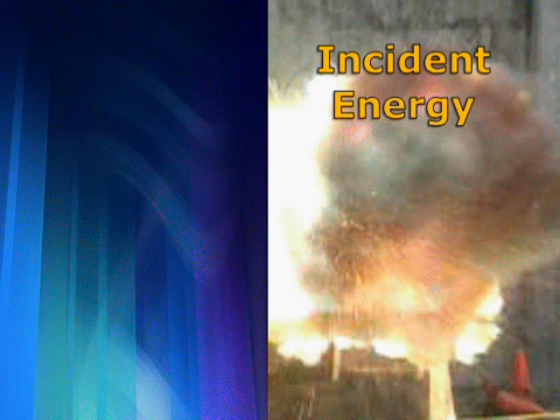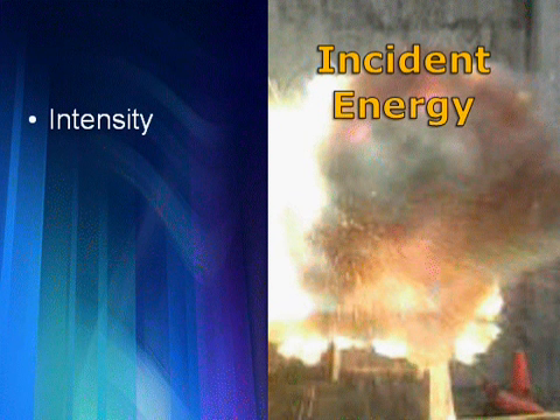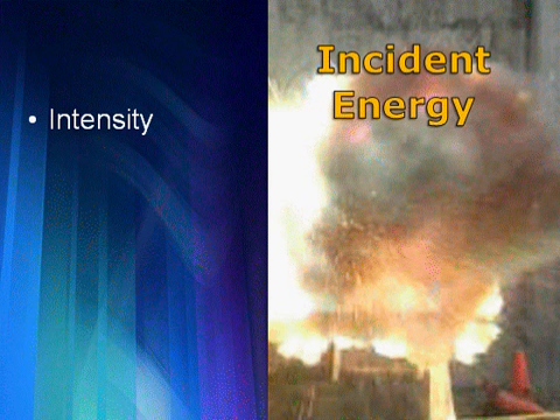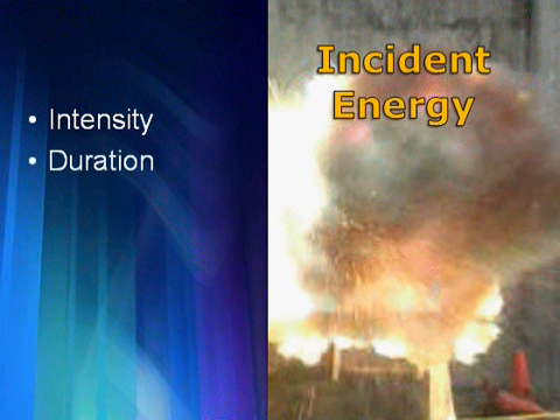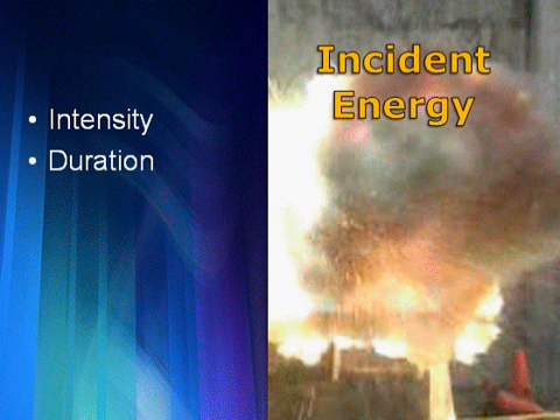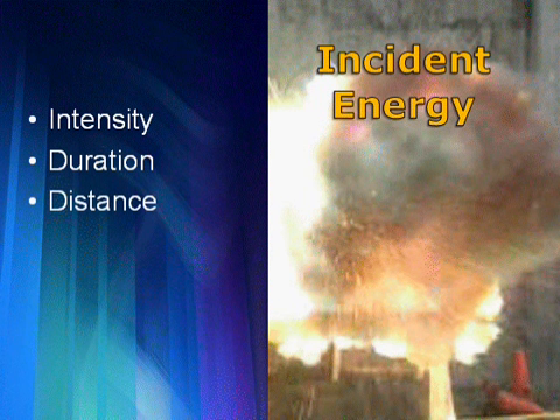You need to factor in things such as intensity. Now, intensity is not, I'll say, an official term, but it's a term that I've used a lot. It's really the short circuit current. The higher the short circuit current, the more intense the arc flash can become, but it's also dependent on duration. When you're looking at strictly incident energy, you can have a lot of short circuit current over a short duration, or maybe a lower short circuit current over a long duration, and you'll have the same amount of incident energy. But a more intense arc flash, well, that's what can lead to the problem with explosive forces.